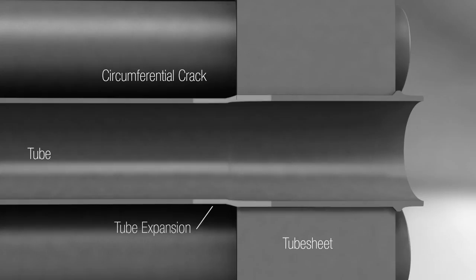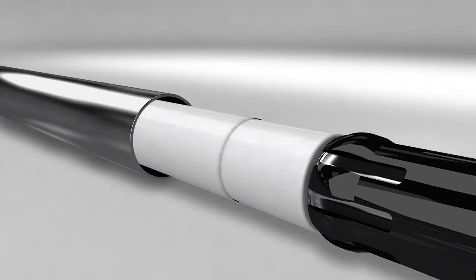Bobbin probes are also sensitive to liftoff, such as the one found in expansion transitions. This is where the patented Defy eddy current array probe comes in. Defy probes incorporate standard bobbin coils and an array of oval coils. The array increases the probe's overall coil density and sensitivity to defects.